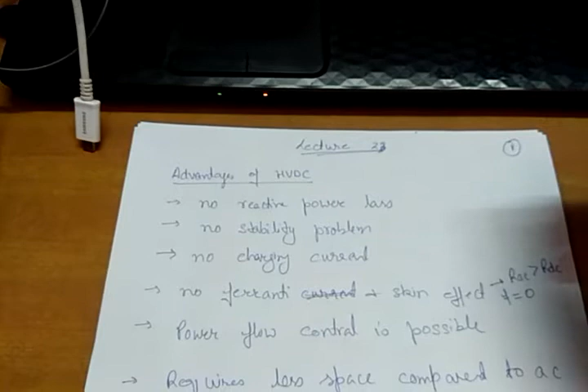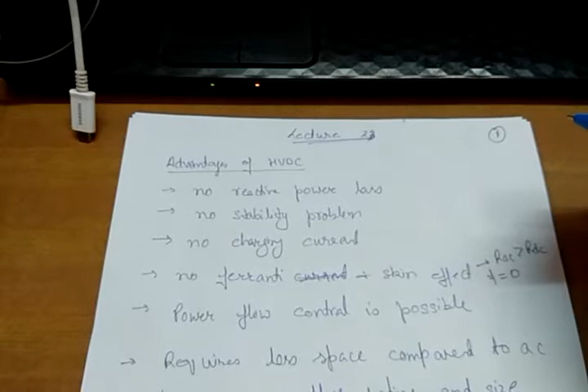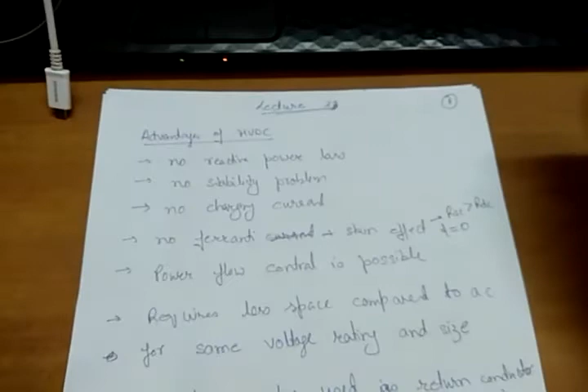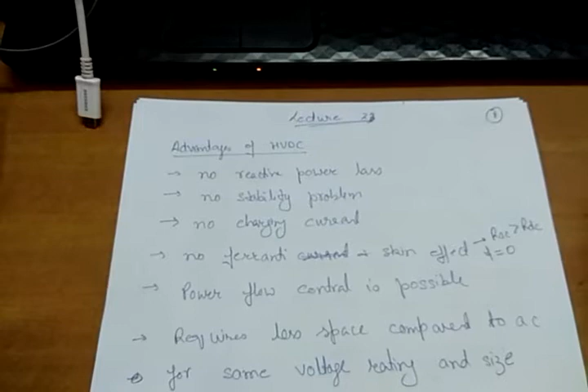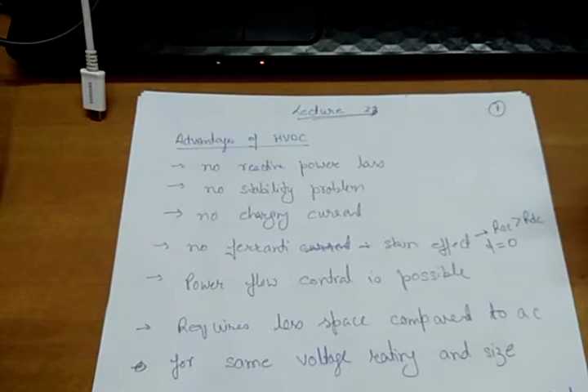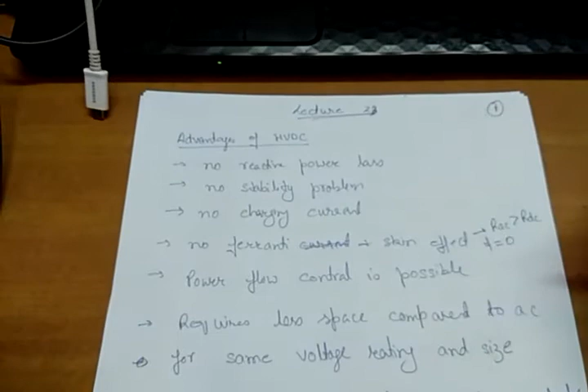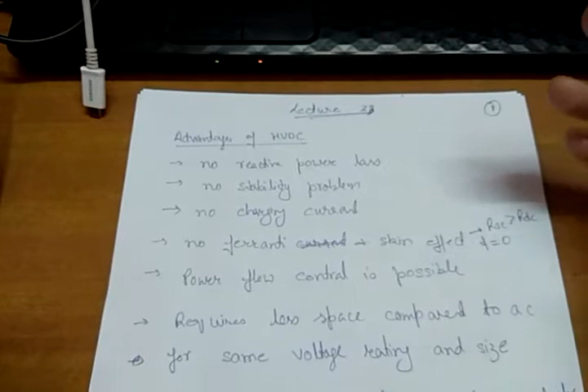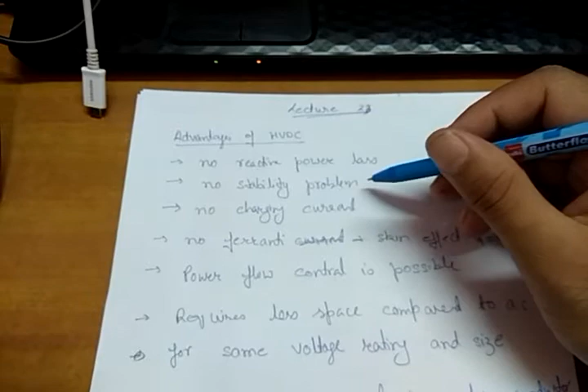I also discussed certain advantages of HVDC, like no reactive power loss, means there is no X, because reactive power loss is given by the formula I square XL minus V square divided by XC. So this reactive power loss is zero in case of a DC system. No stability problem. In case of AC, it is the rotor angle stability delta which comes into picture before the system can reach its thermal stability. Because of this rotor angle stability, the power transfer is restricted. We cannot transfer bulk power because delta is normally operated between 25 to 35 degree. However, in case of a DC, there is no delta, because the power is given simply by VDC into IDC. So no stability problem in DC. The only limit that will govern the power transfer in DC is the thermal limit.